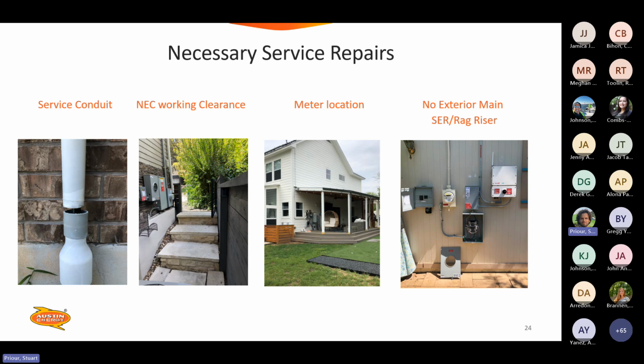So in that case, you'd have to either move that switchgear or find some way to reorient those stairs so that each piece of equipment has a flat working surface. The meter location, that one's kind of tricky to see, but if you look closely, the customer has their revenue meter on that porch right there.